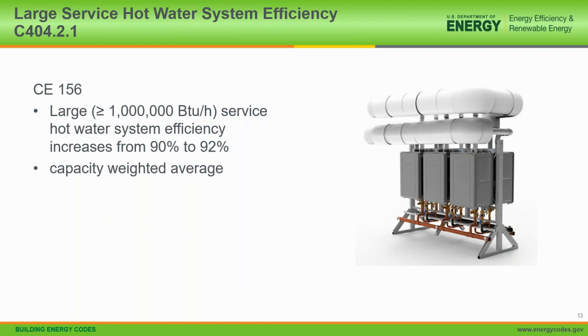And what that means is I could have condensing, which are actually higher, up around 95, 96% efficiency for part of my water heating, and then I might have what you would call a peaking boiler that's less expensive and a lower efficiency that would only come on occasionally during very peak loads, might never come on if the system's over designed, so it would tend to weight that higher efficiency. So it allows for a mixture. It doesn't require everything to be condensing. It's a capacity weighted average. So that again applies only to very large systems.